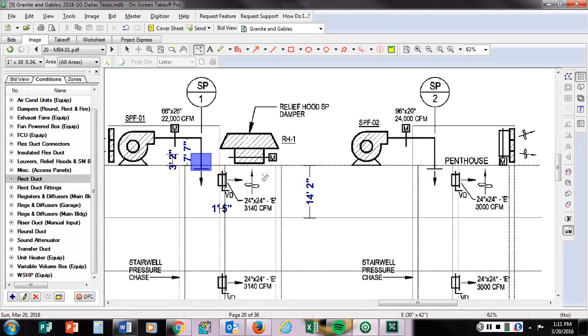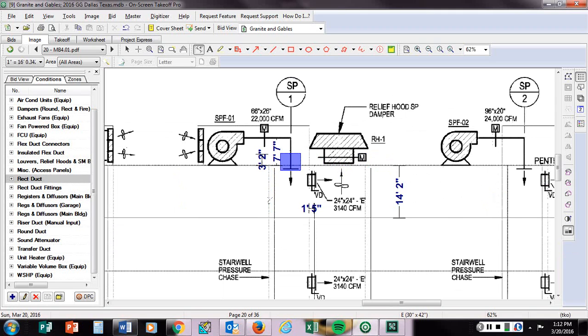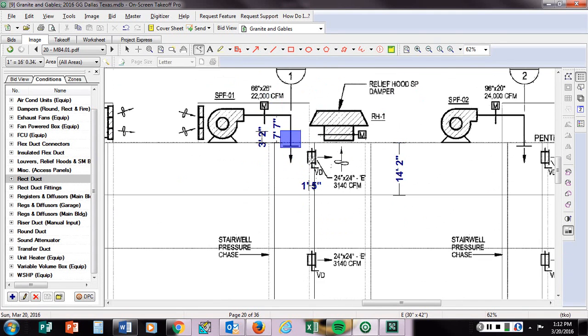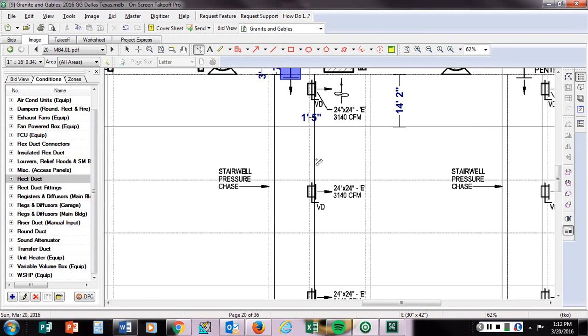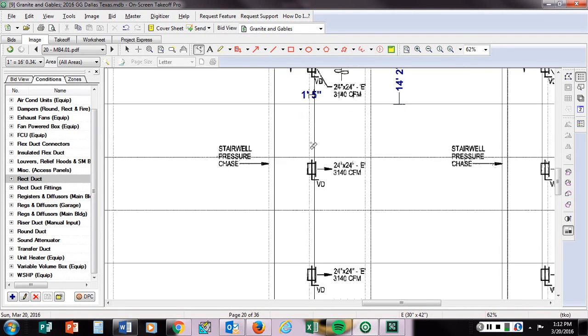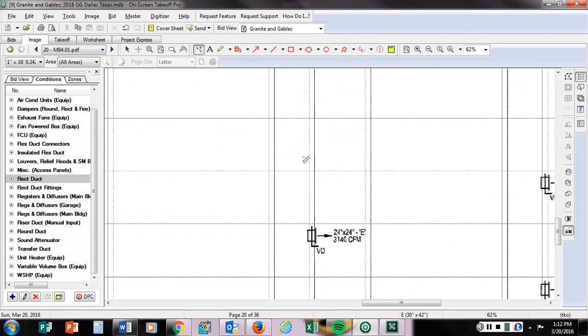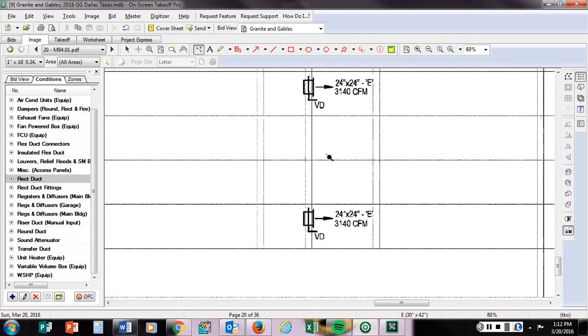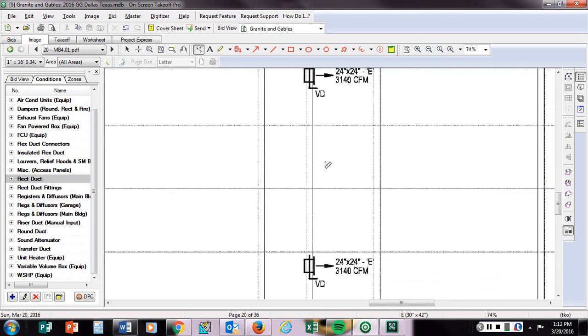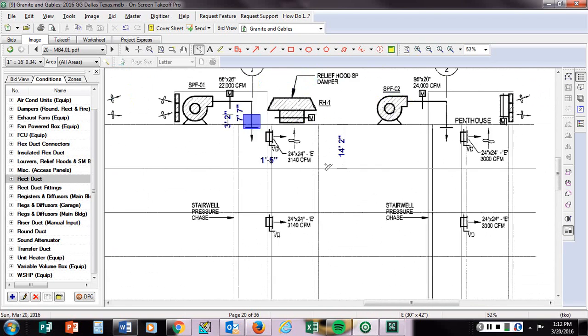So as we go ahead and look at this, we have some horizontal duct. It's going to come down through the roof, and there's no ductwork here like it shows over here. That's because this is just a chase, which is just an opening. It's going to be contiguous all the way to the bottom of the building. They're going to have holes cut into it that are 24 by 24. They're going to have a volume damper for air balancing and a register on them. So the air balancer is probably going to have these more closed, and as you go down the building, they're going to open up more, and it's going to be designed to maintain the pressurization in that stairwell to try to lessen the amount of infiltration that's happening in the building. And you'll see that's going to happen on both of these units here.